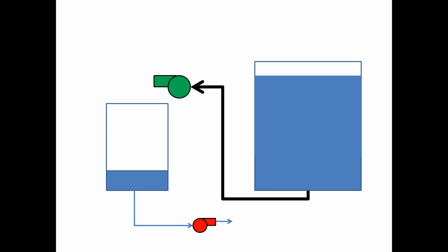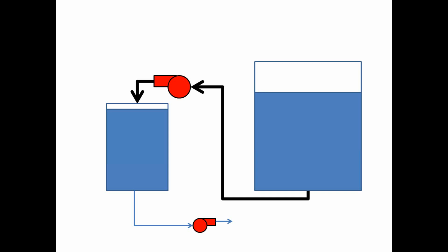What you see right here is a schematic of a chemical day tank. It has a small chemical pump at the bottom of the tank, and it's pumping chemical out of the day tank into the process. There's a large transfer pump that transfers chemical from the large storage tank into the day tank. And right here, there's no instrumentation or anything like this. So what an operator needs to do is keep a close eye on this process so that when that day tank gets low, they can start the pump up and begin to fill the tank up.